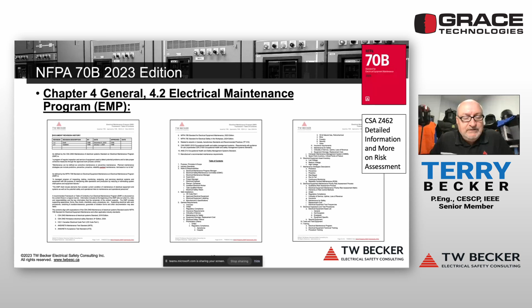Here's a simple process, which is really what 70B is getting you to implement: IC-TOD—inspect, clean, test, operate, and document. We've got 70B for the US, the manufacturer's manuals, and the ANSI NETA Maintenance Testing Specifications.